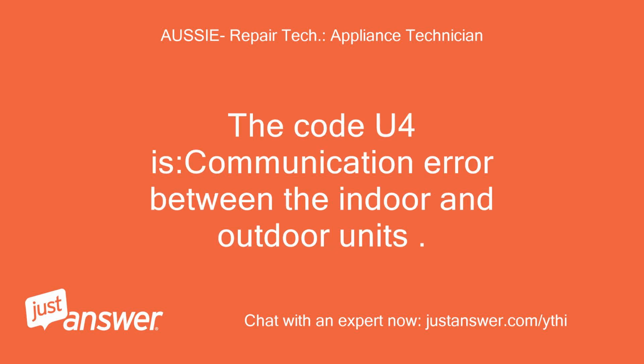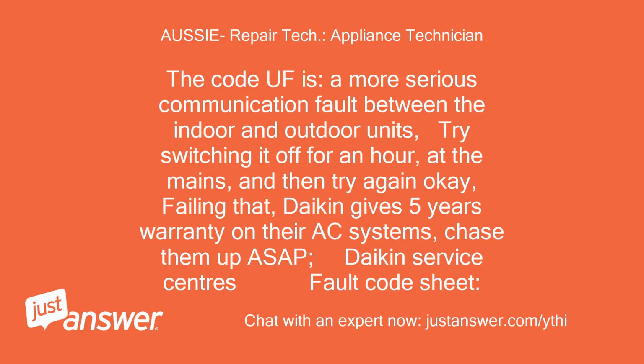The code U4 is a communication error between the indoor and outdoor units. The code UF is a more serious communication fault between the indoor and outdoor units. Try switching it off for an hour at the mains, and then try again. Failing that, Daikin gives 5 years warranty on their AC systems. Chase them up ASAP. Daikin Service Center's fault code sheet.